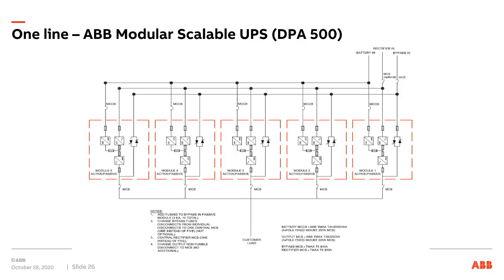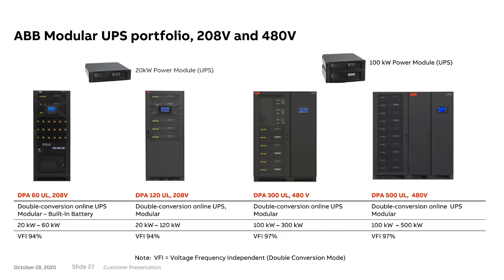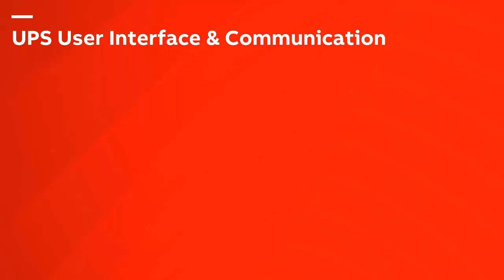So this is fully populated. Of course, this could have started out with 1 or 2 modules and then space to add more. Same as I showed for the ABB offering for monolithic, this is the ABB offering for modular. The 20 kW module is used in the 60 and 120 kVA frame, 208 in and out. The 60 has space for built-in batteries. The other 3 frames require external batteries, like most bigger UPSs. And then the 100 kW module is the basis for the 300 kW frame and the 500 kW frame, all of the modular scalable products.